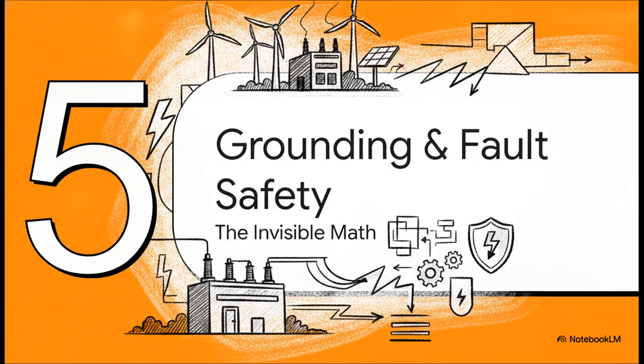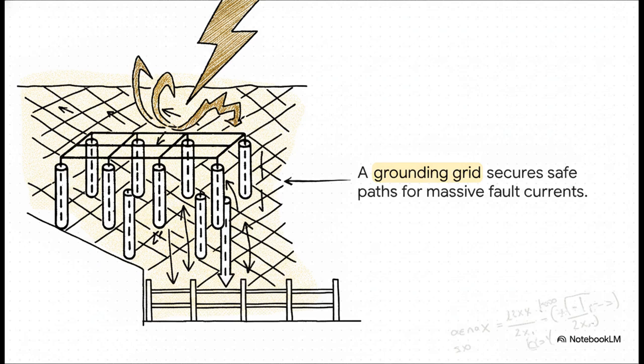Which brings us to our final section, grounding and fault safety, or what I call the invisible math. When a massive short circuit hits a substation, like a direct lightning strike or a severe fault, thousands of amps need somewhere to go instantly. Beneath the substation is a massive buried mesh of copper wire and deep ground rods, extending well past the fence line. Its entire job is to secure multiple paths for fault currents to safely enter the earth, neutralizing the danger before it electrocutes workers or destroys equipment.